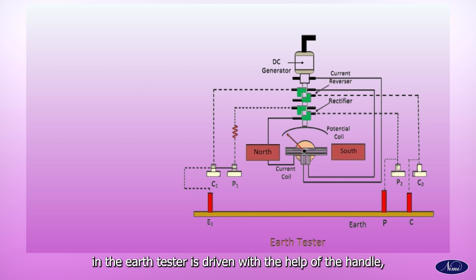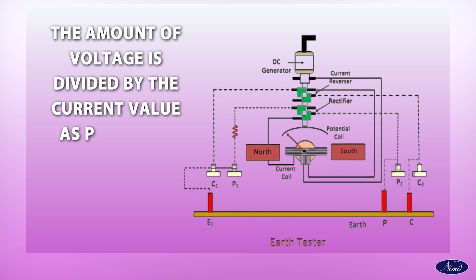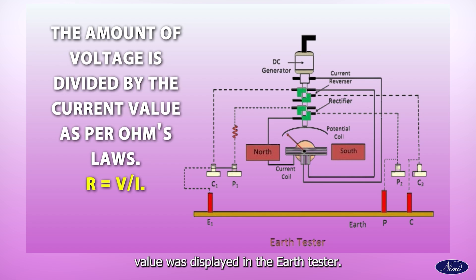When the DC generator in the Earth Tester is driven with the help of the handle, it will produce the electromotive force or voltage which will cause the current to flow to the Earth through the Earth rod. The amount of voltage is divided by the current value as per Ohm's law: R equals V upon I. The calculated resistance value is displayed in the Earth Tester.